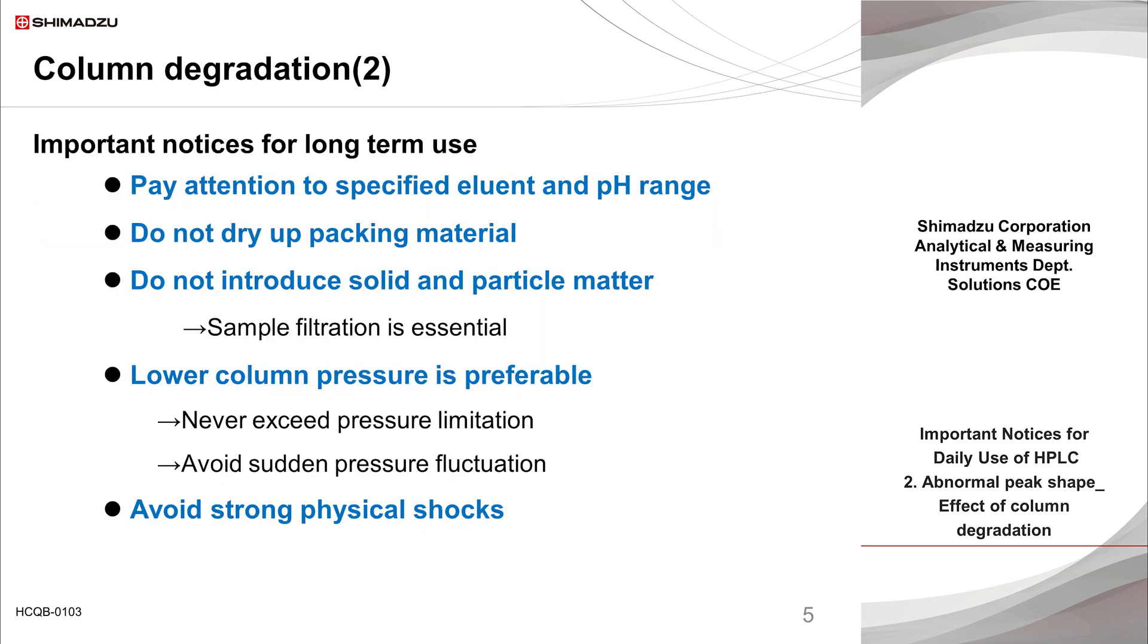It is essential to follow the precautions listed here to avoid common causes of column degradation as shown in the previous slide and ensure long column lifetime and stable performance. As you may already know, it is important to increase the flow rate gradually when starting mobile phase delivery to avoid sudden pressure increase. Similarly, sudden pressure drop may seriously damage the analytical column as well. If you intend to open the drain valve after stopping the mobile phase delivery, you should wait until the remaining system pressure drops close to zero before doing so, to avoid risk of column deterioration.